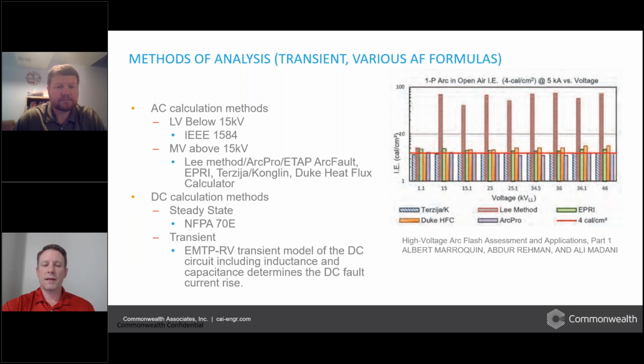The other way we can look at it is if the DC arc flash is too high, we can do a transient analysis of it, where we basically look to see how high or how fast the fault current rises, and if the fuse blows before the fault current is even at its highest, we can get a better result.